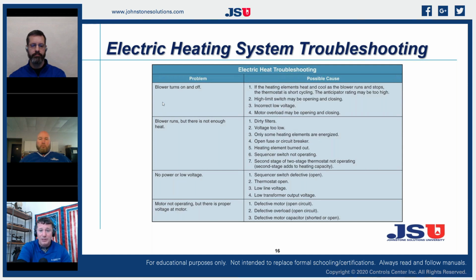And no power or voltage, man, I've seen so many times that those heat sequencers have failed, and that is just a switch. That's just a contact. So if our heat sequencer is failing, it will not bring on our heating elements, or it'll have a voltage drop across it, which reduces our voltage, which now is going to reduce our total wattage. And motor not operating, but there's proper voltage at the motor. Well, then we've got to get into our controls, capacitors, and modules. It's on the back of those ECM motors. So just a little bit of info on troubleshooting an electric furnace.